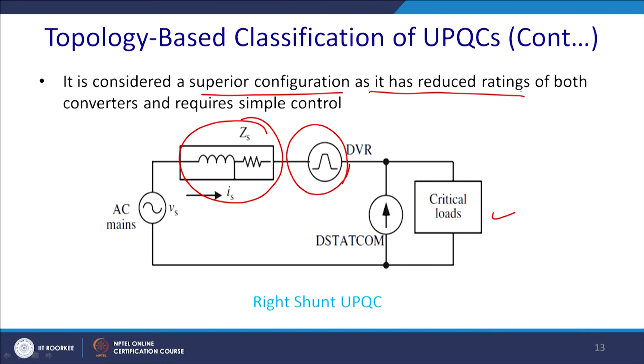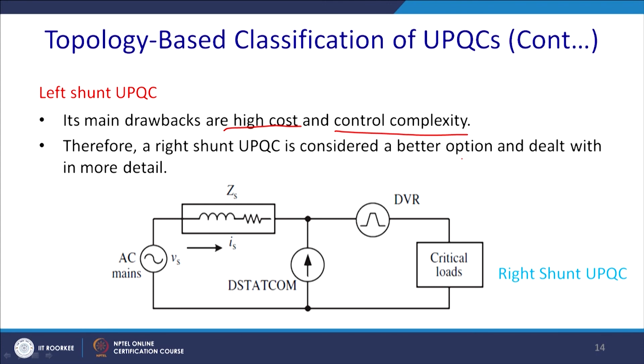So, it is considered the superior configuration as it reduces the rating of both converters and the control is quite simple, because you have already mitigated the voltage and thus you are getting a clean voltage, and then the STATCOM has to control only the issues related to the current. And in the same way we can have a left shunt. So, this is the combination. The main drawback of this is high cost and control complexity. Therefore, the right shunt UPQC is considered the better option to deal with. So, this is the right shunt UPQC.